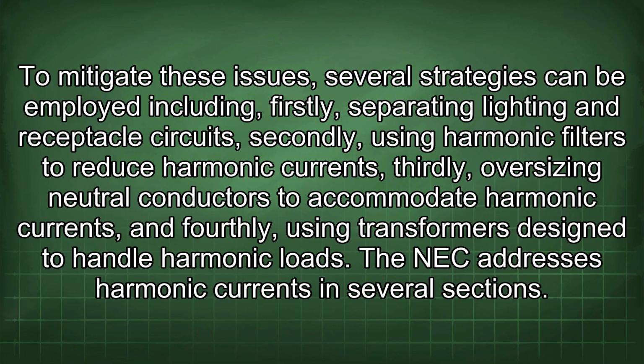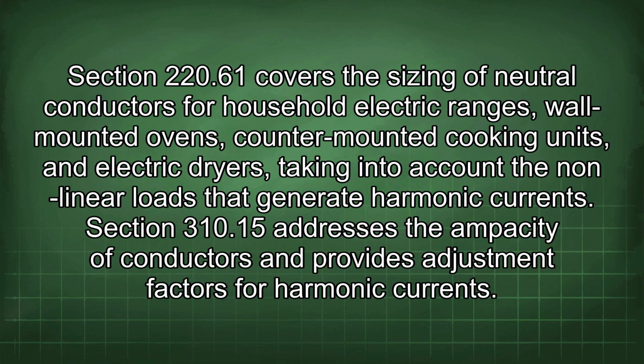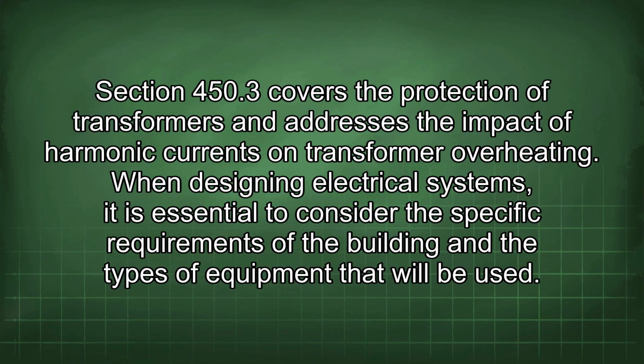The NEC addresses harmonic currents in several sections. Section 220.61 covers the sizing of neutral conductors for household electric ranges, wall-mounted ovens, counter-mounted cooking units, and electric dryers, taking into account the nonlinear loads that generate harmonic currents. Section 310.15 addresses the ampacity of conductors and provides adjustment factors for harmonic currents. Section 450.3 covers the protection of transformers and addresses the impact of harmonic currents on transformer overheating.